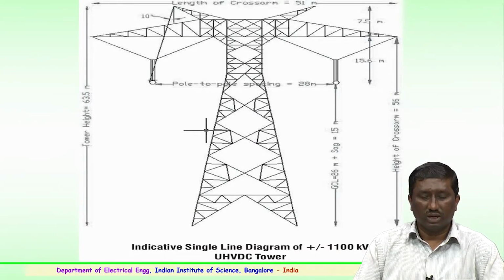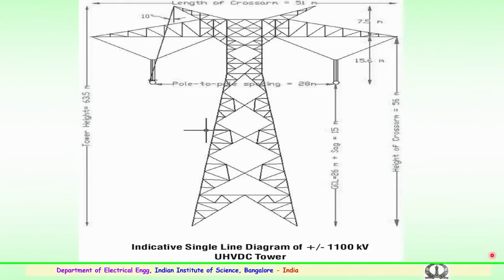This is again further we were discussing the 800 kilovolts DC line and the 1200 kV AC line. Further, in the country there is a thought that HVDC lines for long distance transmission are much more economical and more power could be transferred by going in for HVDC lines. So, it is thought by the utility and the government to further consider this in case of large power transfer.